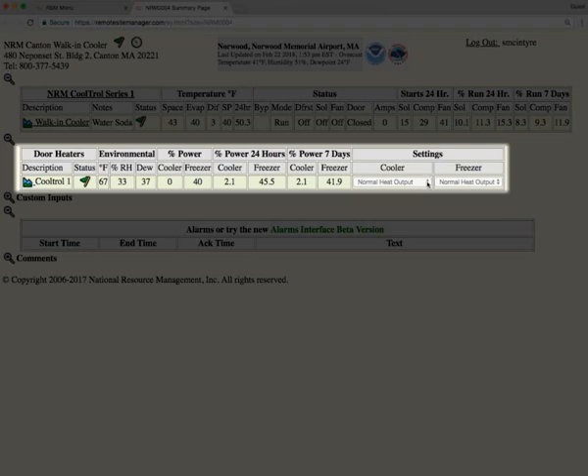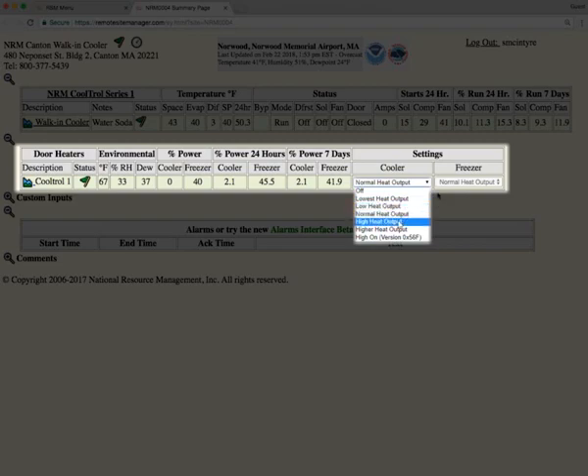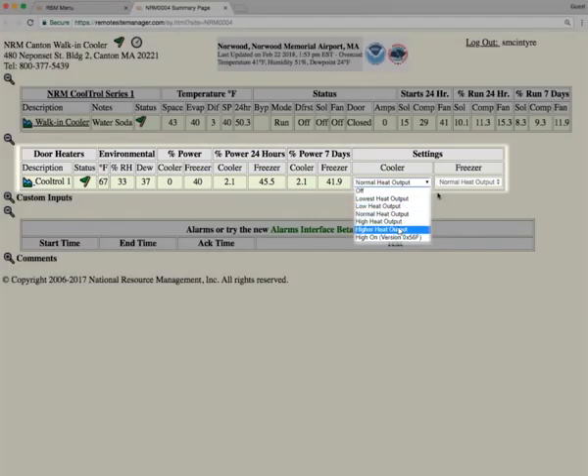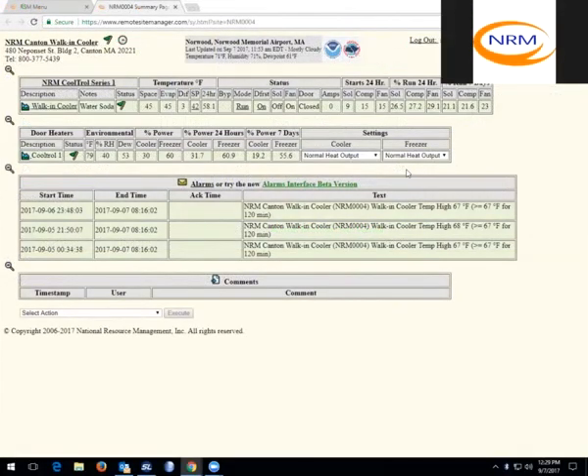You can also adjust the heat output. From the factory, it is set for normal heat output. If you have issues with the door heaters, condensing or icing up, you can raise the heat output and the door heaters will run at a higher percentage to help eliminate those issues.